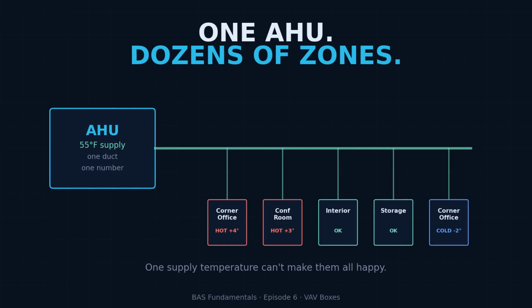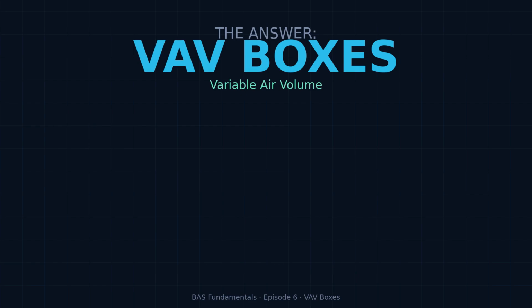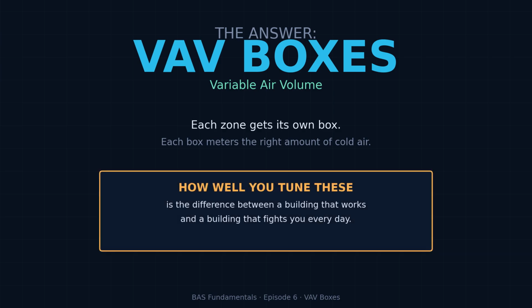Your AHU delivers one supply air temperature, usually 55 degrees, one duct, one number, one big fan pushing cold air into the building. But your building has dozens of zones, corner offices that overheat from solar load, interior conference rooms packed with bodies and laptops, storage closets that need almost nothing. One supply temperature can't make them all happy. So how does every zone get exactly the right amount of cold air?